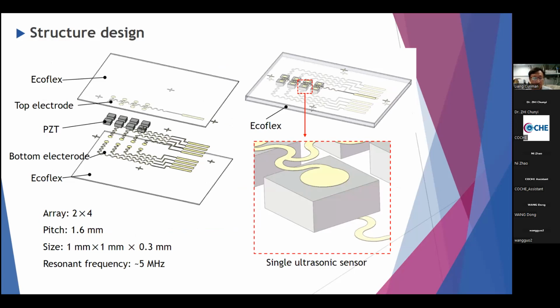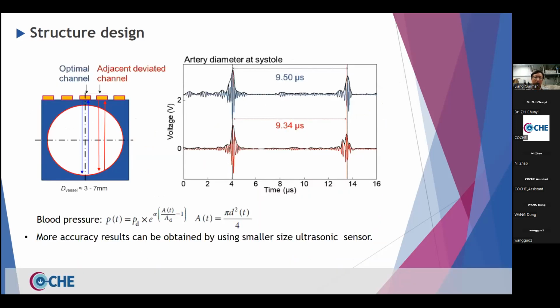The sensor array contains 2x4 transducers. The size of each transducer is 1 by 1 millimeter, and the pitch is 1.6 millimeter. The thickness of the transducer is 0.3 millimeter, and the resonant frequency is about 5 megahertz. This picture shows the working principle of the ultrasonic sensor. The ultrasound sensor is designed as an array type, aiming to map the vessel position, which enables sensing and monitoring by a sensor overlaying the targeted vessel without manual positioning.